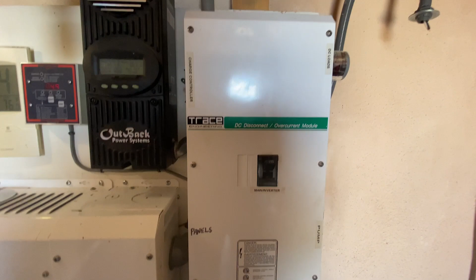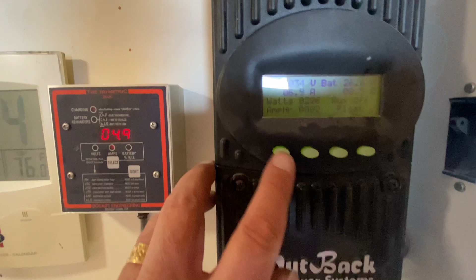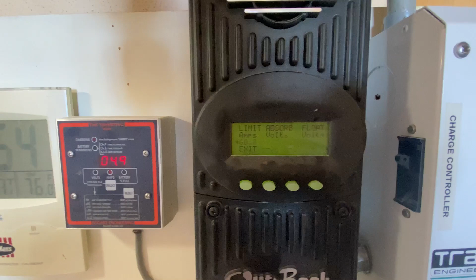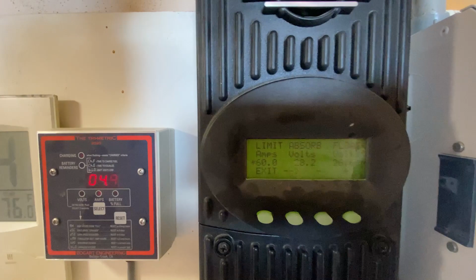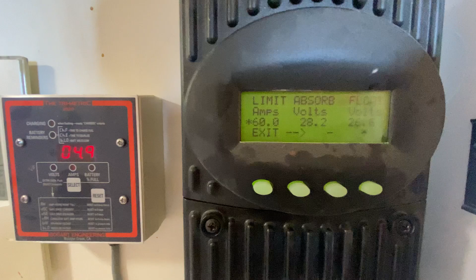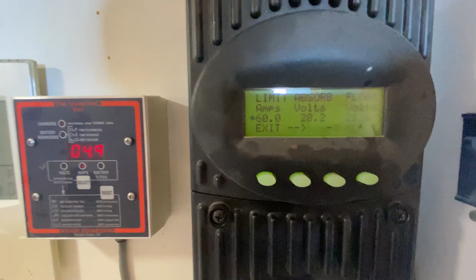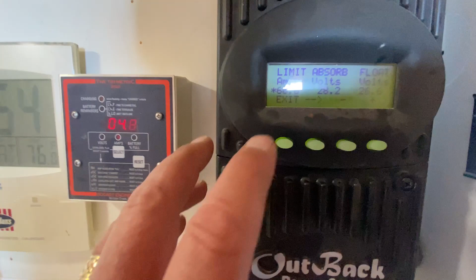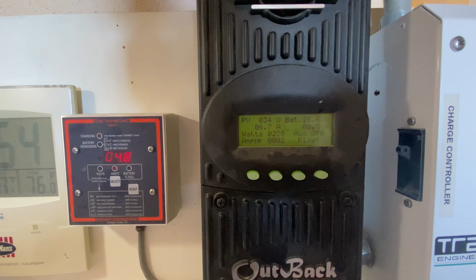So we've routed this into our junction box here, or DC disconnect overcurrent module in Trace Engineering terms. Then we moved on to the Outback FM60 charge controller. What I did there is set the absorption voltage to 28.2, and the float voltage, which of course you really don't need to float lithium batteries, is now set to 26.6.